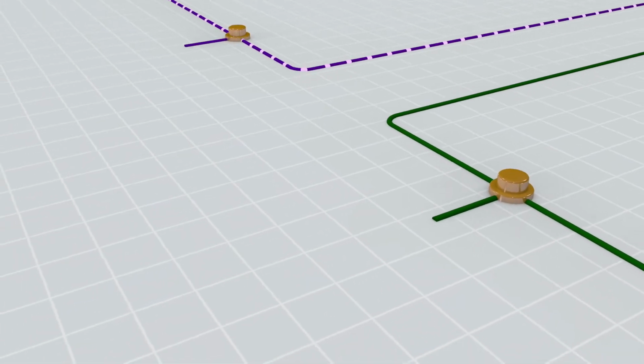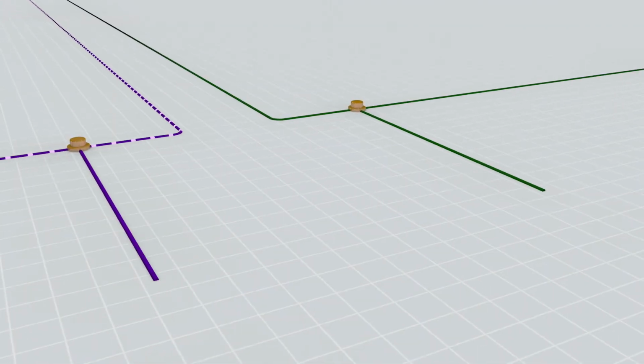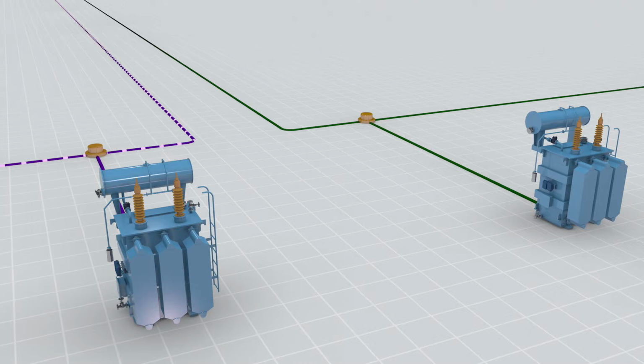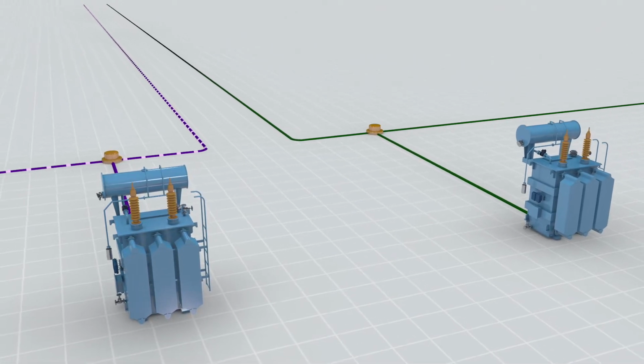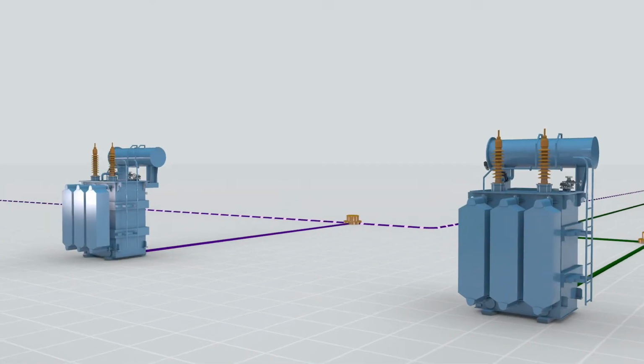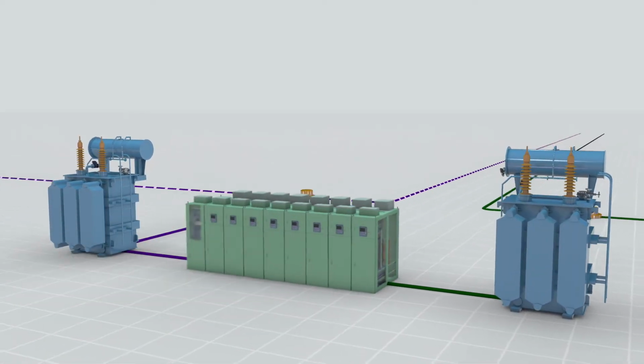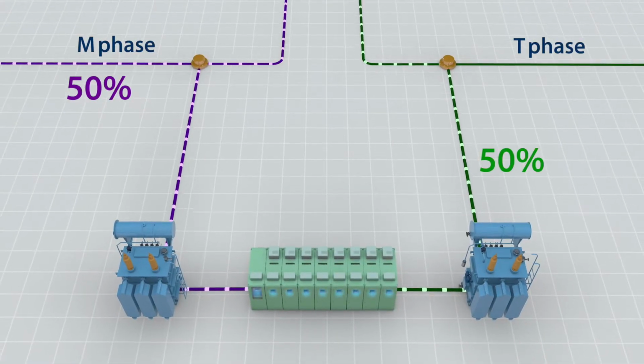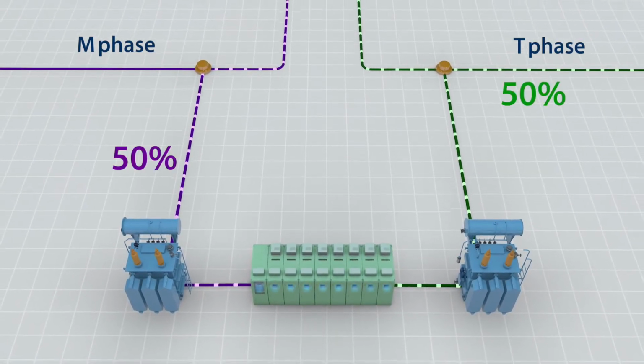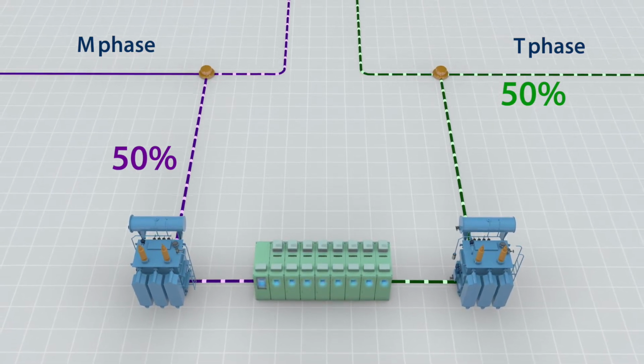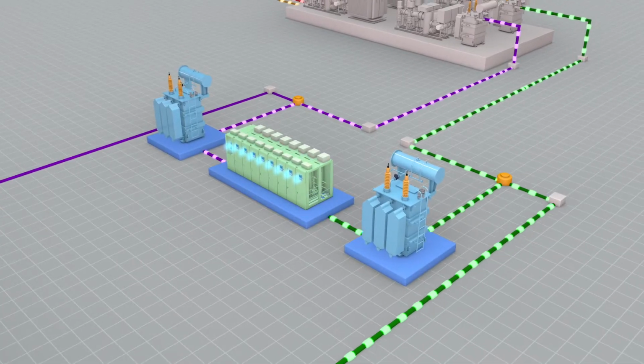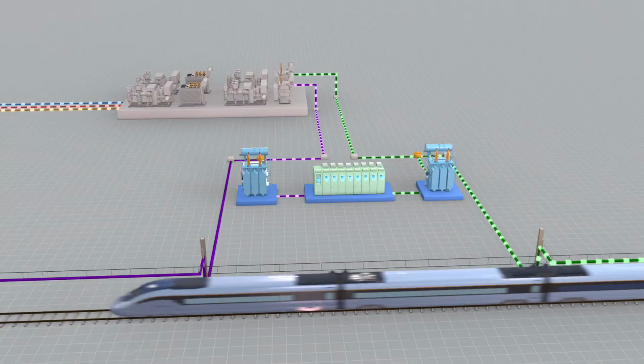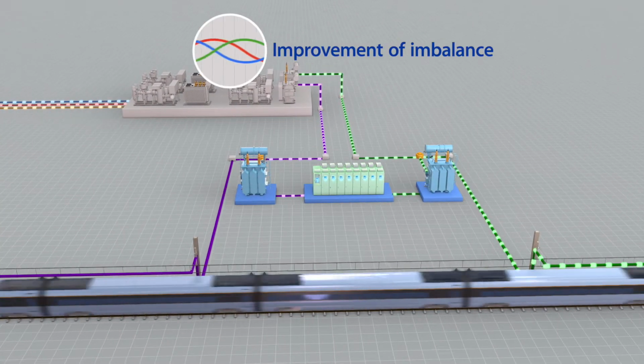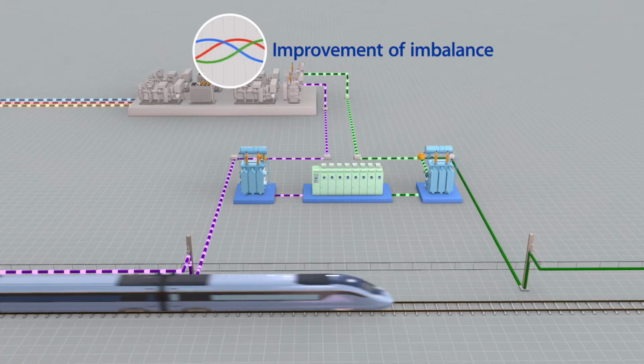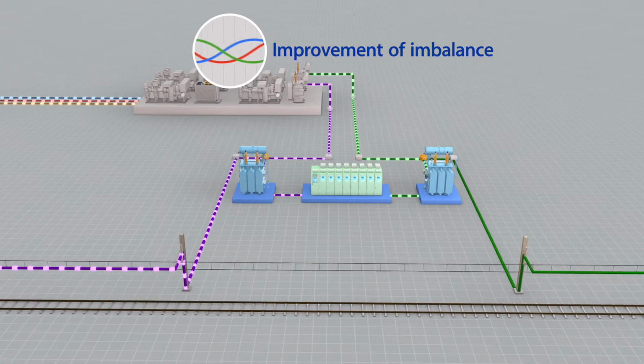The multi-winded transformer, which comprises an active balancer, converts the high voltage properly for the voltage of the single-phase inverter, and it transforms the phase value in real time through the back-to-back inverter system, providing stable power to the M and T phases respectively. It improves the imbalance of three-phase power by drawing power from feeder lines with low loads and supplying it to feeder lines with high loads.